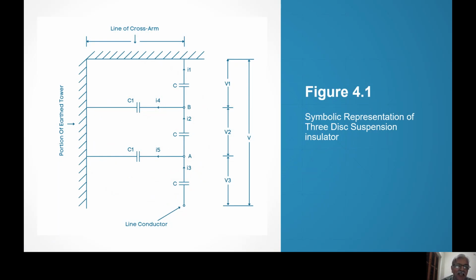So symbolically, it is like this because after all, the porcelain is a capacitor, and the air between the metal part and the grounded tower is also a capacitor. So C, these three are the porcelain mutual capacitors, shunt capacitances of the porcelain. C1 and C1 are, because the distance is the same, these two capacitances also remain the same. C1 and C1 are the stray capacitances. The value of C1 is such that the current passing, I5, is very low with reference to I3. So there is not much difference between I3 and I2. But I2 is certainly less than I3 because of leakage of I5. And I1 is certainly less than I2 because of leakage at I4.